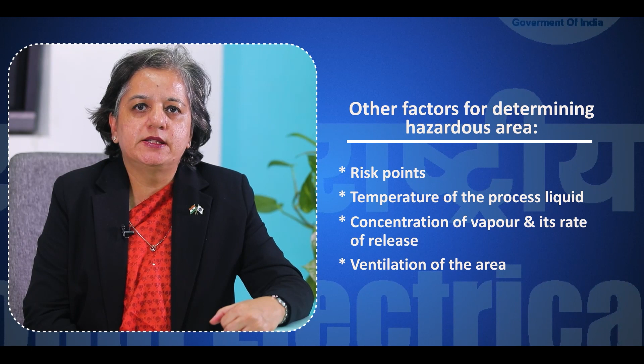In addition to the properties of flammable materials involved, many other factors such as risk points, temperature of the process liquid, concentration of vapor, its rate of release, ventilation of the area, etc., need to be considered for determining the degree and the extent of hazardous areas while applying the guidelines given in IS 5572, which is the Indian standard for classification of hazardous area.